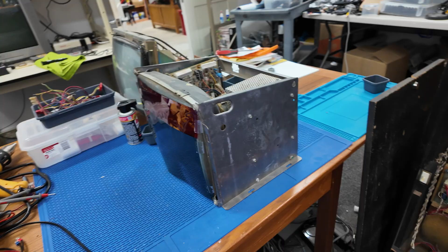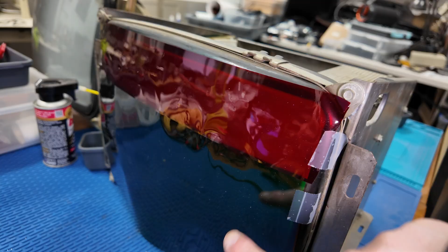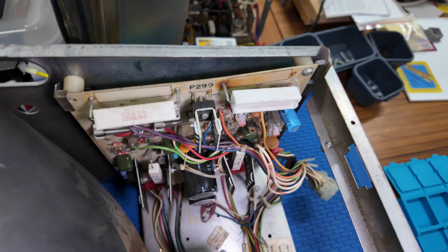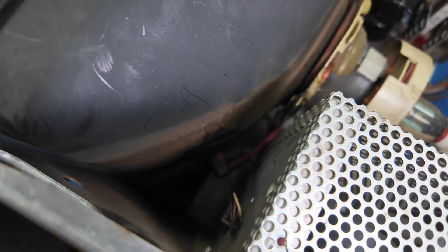All right, we got the monitor on the table here next to the game. This is what I was referring to about the gels. This is a red filter, and then we got a green filter down here that gives the color to the monitor. We can take a quick look inside, see what we've got going on here. That's interesting. The anode suction cup, it looks like it's not fully inserted into the tube.